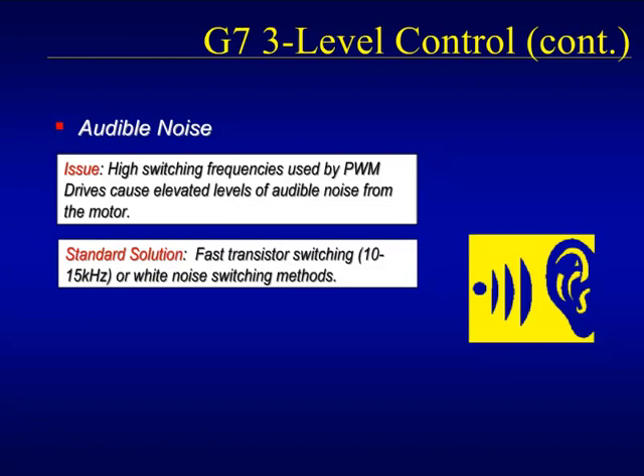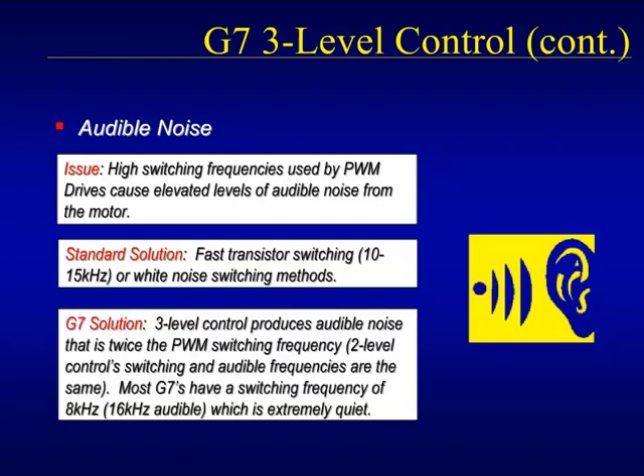Increasing the switching frequency is not possible with most larger motors and will probably increase heating in the drive itself. Another solution to the audible noise problem that came from the drive industry was referred to as white noise switching. White noise switching would modify the characteristics of the noise to make it more acceptable, but did not reduce the level of noise appreciably. The solution offered by the three-level G7 comes from a unique switching pattern that makes the audible noise shift to a frequency that is twice the actual switching frequency and is out of most humans' hearing capabilities.